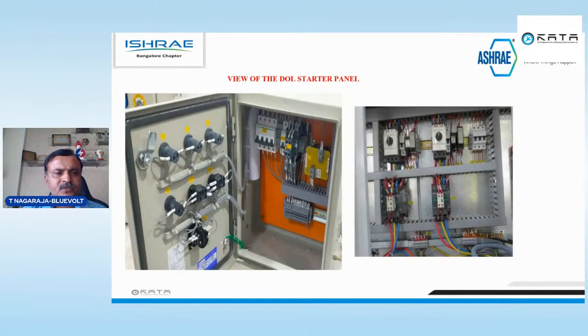This is one view of the DOL starter panel. See, I told you 3 phases, R Y B, then the push button which is showing at the backside, then trip, auto manual switch, MCB, then control MCB, contactors, then overload relay, connectors, and one transformer for the 24 volts valve or fire interlocking purpose. This is one type of starter. This is the other type of DOL starter.